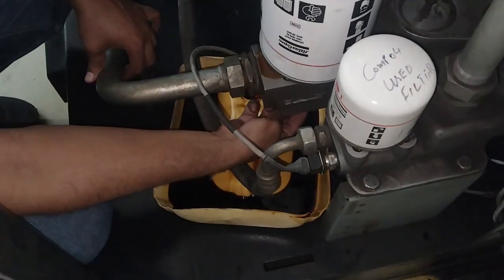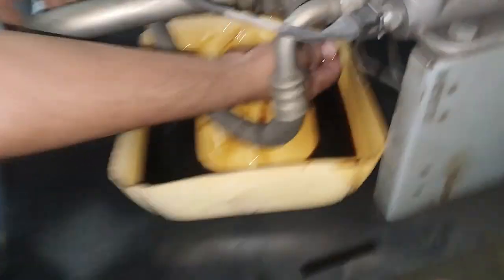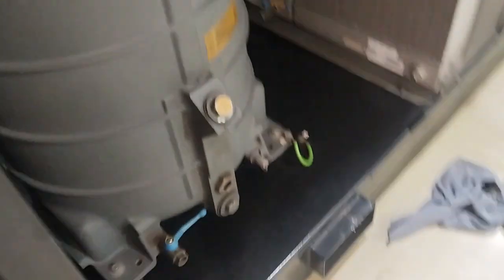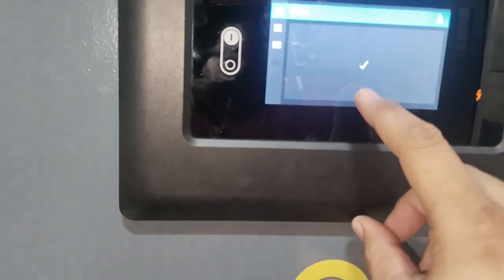After replacing the filter, you must check all other things: make sure the drain valve is closed, and the compressor outlet valve is open. Now we are going to open this valve for startup. The valve is open — check the sight glass; the oil level is okay. The oil cooler is clean and the temperature sensor is installed properly. Remove any cotton particles if present, check all things, then remove the emergency stop and reset. Now we are going to adjust the set points of the compressor.